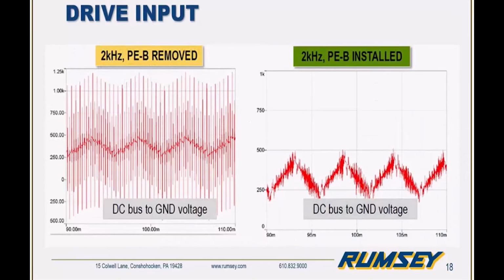Here's an example of a solidly grounded system. On the left-hand side, we have the drive without that PEB jumper installed, okay? So we can see voltage spikes on the DC bus are exceeding 1,000 volts. On the right-hand side, we have the same drive, solidly grounded, with the PEB jumper installed correctly, and we can see that the voltage spikes have been decreased and peaks are below 500 volts now. So again, critical to make sure we have the drive configured and installed correctly for its system.